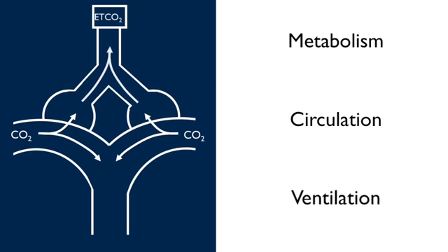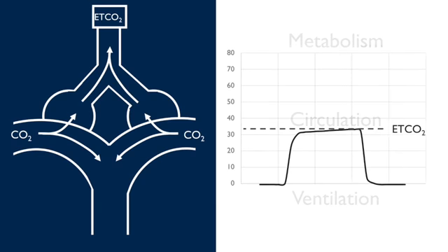Graphically, we get something that looks like this, where a plateau is formed during expiration, and the end tidal CO2 is recorded at the end of that plateau. During inspiration, the reading should be 0 because typically we are breathing negligible amounts of carbon dioxide.